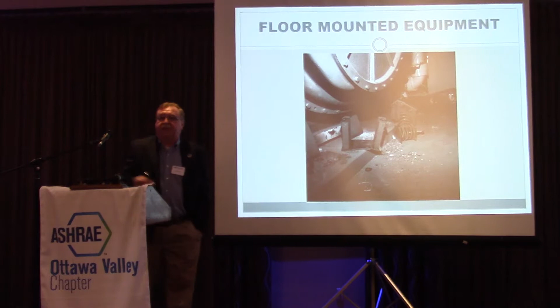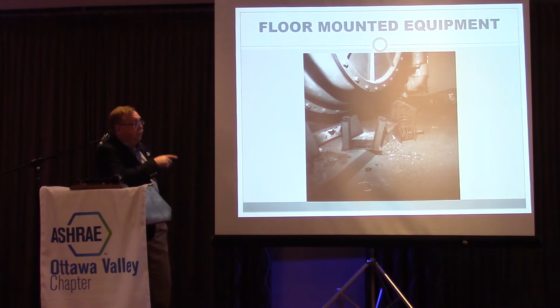So ASHRAE put together a standard, which I'll go over in a minute. I chaired that for both cycles because I wanted to make sure to get rid of junk like this, and junk like this—what we call OEM equipment. You buy a piece of equipment and they say, sure, we'll give you the vibration isolation with it, no problem. Then you get junk like this that doesn't even have a bolt hole, just a little indentation for a slot on the end of the equipment, and it wasn't even bolted down, so this thing went all over the place.